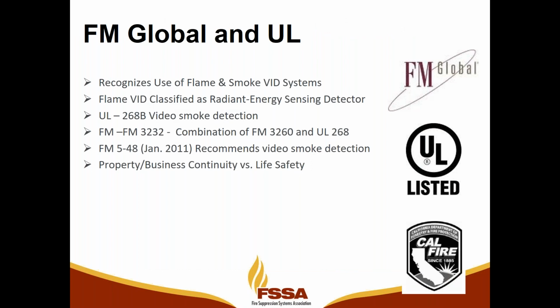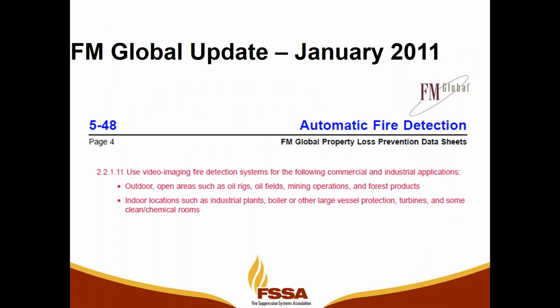So UL and FM have approvals for video analytics. UL 268B is specific for video analytics smoke detection. UL uses FM 3260, which is the radiant energy flame standard. And then FM has a new standard, 3232, which includes both video smoke detection and flame detection. FM datasheet 5-48, represented here, specifically recommends using video image fire detection in industrial applications.